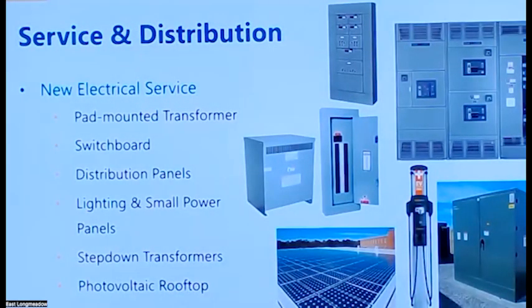So now, again, high level: the service and power distribution system, and the components of that. The electrical service obviously will be coming from National Grid. It will be a new service. The existing service will stay in place because the existing school will operate during construction. So the new transformer will be installed, and the new service will be provided. I'm already in contact with National Grid. There's already a work order, they call it a work request, initiated. I'm already submitting documents to them.